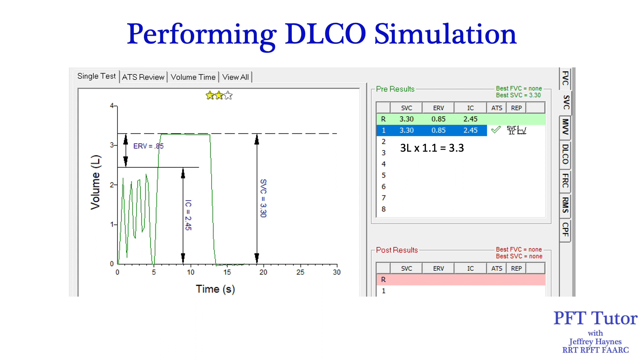When you do this, you'll notice that the vital capacity will be higher than 3 liters — it should be about 3.3 liters. The vital capacity will be 3.3 because this is being performed in patient testing mode, and in patient testing mode, the measured volumes are multiplied by the BTPS correction factor, which is generally around 1.1. As you can see, the 3-liter simulated vital capacity is reported at 3.3 liters. Remember that a spirometer malfunction may also affect DLCO, so if the simulated vital capacity is not close to 3.3, you may have found the problem without even doing the DLCO simulation.